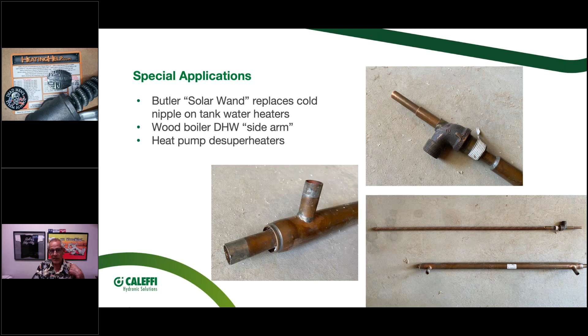Just enough to be warm when you're in the shower or the tub. So now you've got a pretty big delta T to work with, if I have 190 and I've got the full output of the boiler. I'll switch off the heating load, usually with one of these diverting valves, so all the output of the boiler goes to the heat exchanger, at the highest temperature that boiler can comfortably run at.